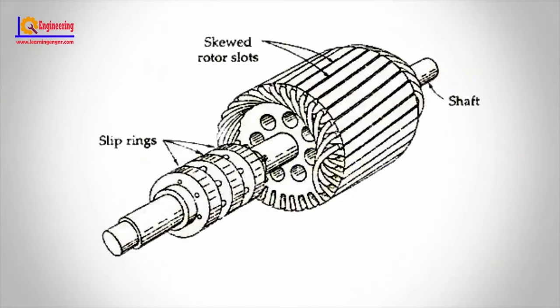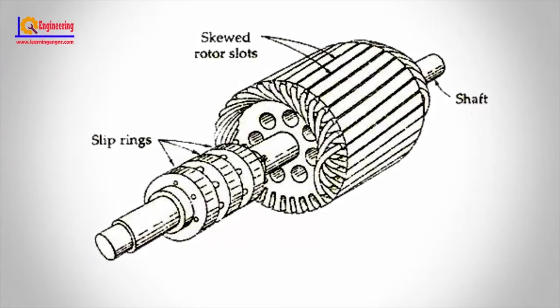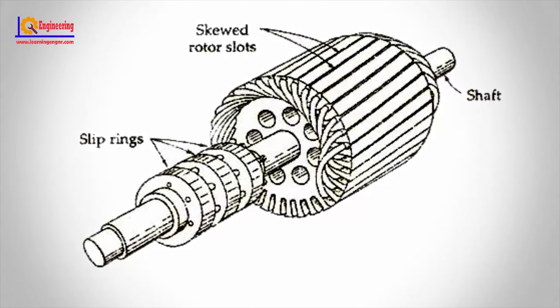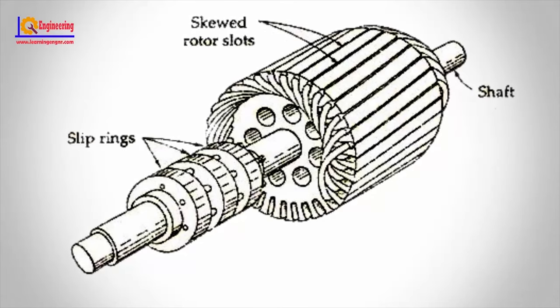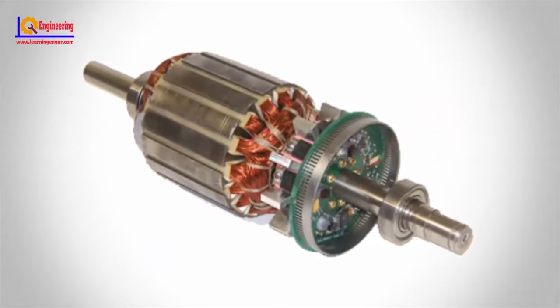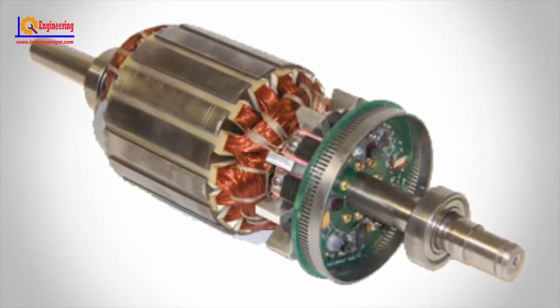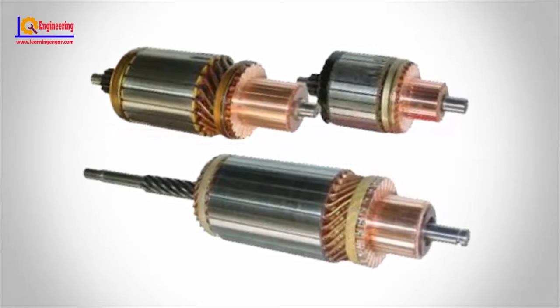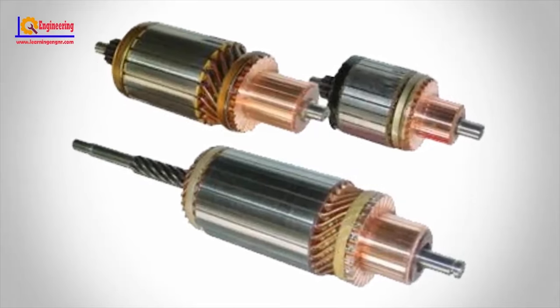Wound rotor: The rotor is a cylindrical core made of steel lamination with slots to hold the wires for its three-phase windings, which are evenly spaced at 120 electrical degrees apart and connected in a star configuration. The rotor winding terminals are brought out and attached to the three slip rings with brushes on the shaft of the rotor. Brushes on the slip rings allow for external three-phase resistors to be connected in series to the rotor windings for providing speed control.